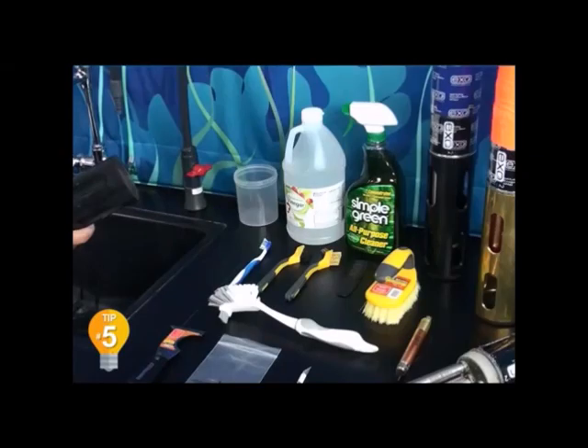So what are the typical tools needed to keep your instrument clean? Well, you can buy most of them at your local store. This would be things like mild dish soap, a dish brush, plastic putty knife, and clean water - tap water is perfectly fine. Also a non-abrasive scouring pad, the manufacturer-issued CT brush, grease, and syringe. And if you're in a high carbonate environment, something like white vinegar or a 1 molar solution of hydrochloric acid works well to break those down.